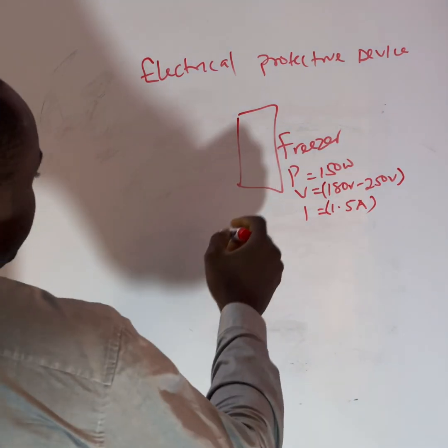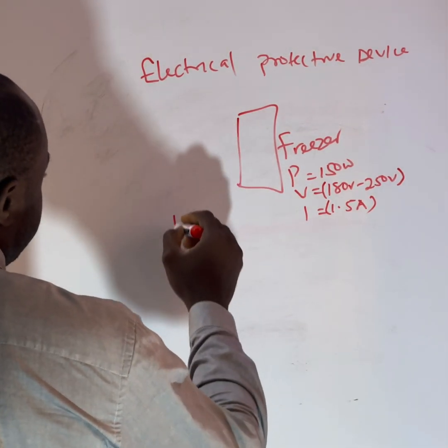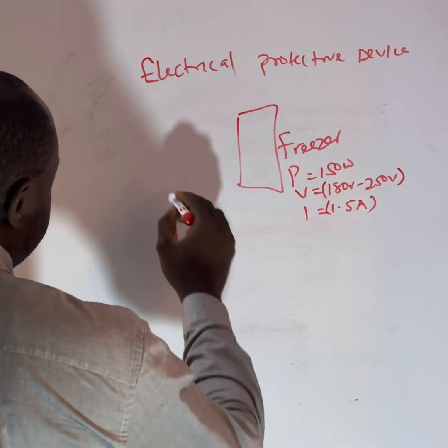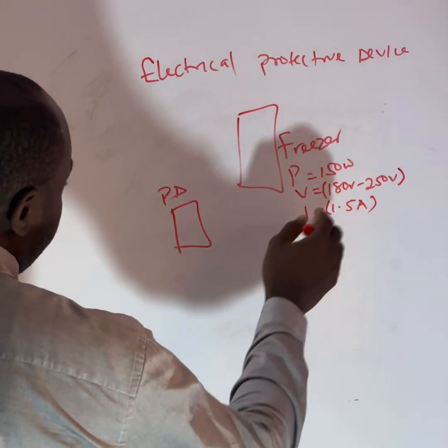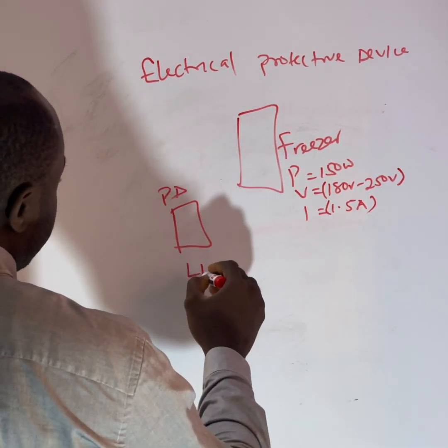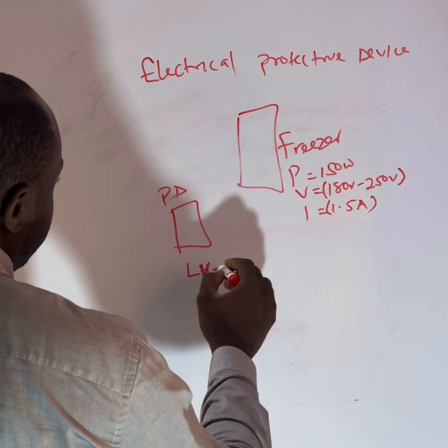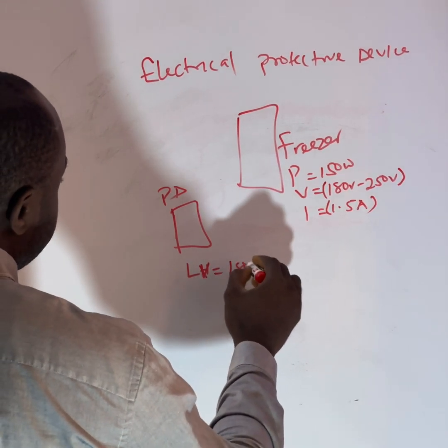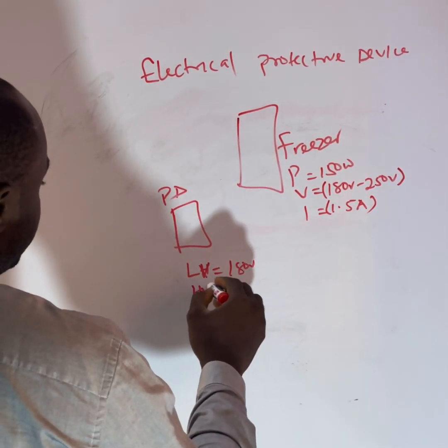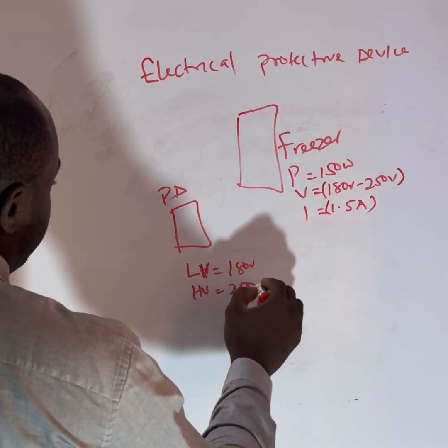It means that in the programming of the device—this is your protective device—you are going to set the low voltage, LV, to 180 volts and the high voltage to 250 volts.